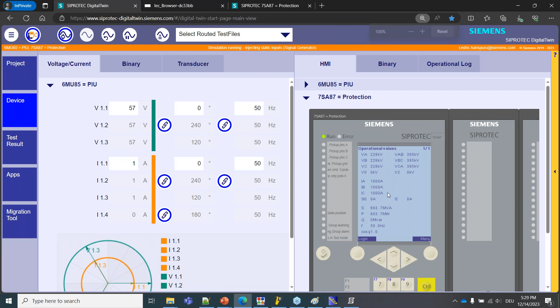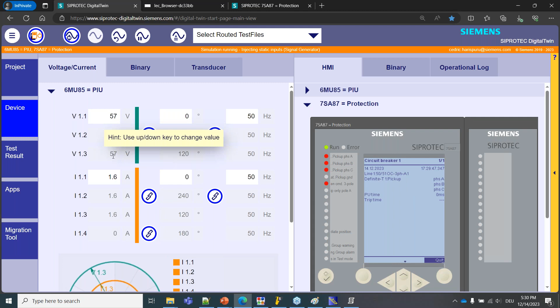And to validate that the values are transmitted, I can see in the display, if I increase the secondary values for the current, it's reflected, the primary values are getting higher. And as some overcurrent protection has been configured, here it is showing, for example, that the sampled values are transmitted and the threshold used for the overcurrent protection is correct. And that way, I can test various protection applications.